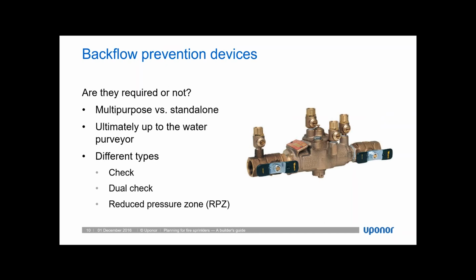Backflow prevention devices are something that you will only usually see for standalone sprinkler systems. They are not actually required in the NFPA 13D standard. This is something that is a requirement of your local water authority. And it's not a guarantee that using a multi-purpose sprinkler system will exempt you from their requirement to use backflow prevention. In some areas, backflow prevention is required regardless of whether a sprinkler system is installed or not.